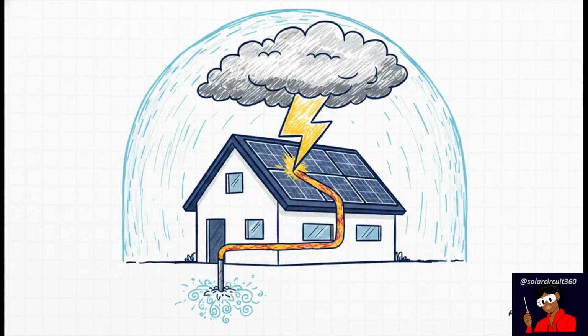And this brilliantly illustrates the difference between just checking a box for a local inspector and actually ensuring your solar array is safe holistically. When done correctly, a proper earth ground is an active defense mechanism. True protection means you're building a low-impedance path for everything nature and mechanics can possibly throw at you. It's not just about a wire shorting out. A solid, low-resistance ground is the exact same path that lightning surges use to harmlessly enter the earth instead of completely frying your expensive solar inverters. It's the path that clears inverter faults and protects the surge devices guarding your entire home.